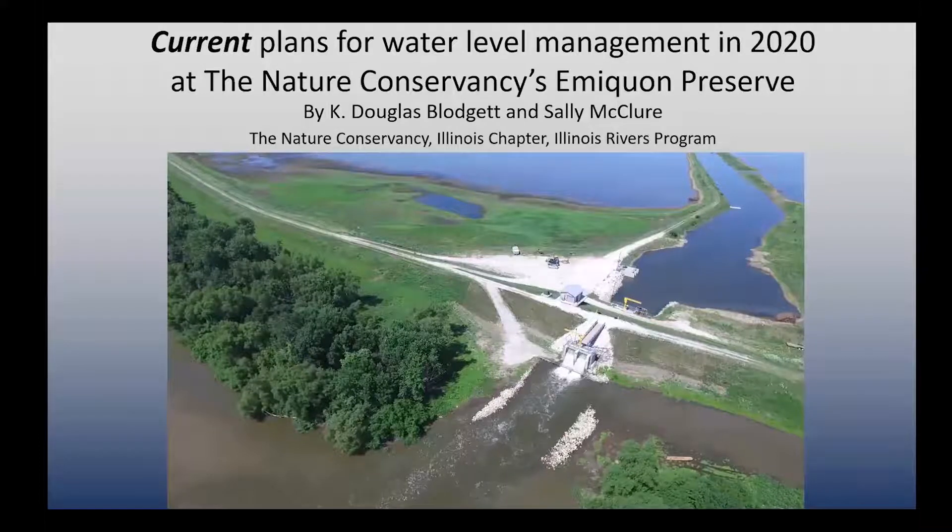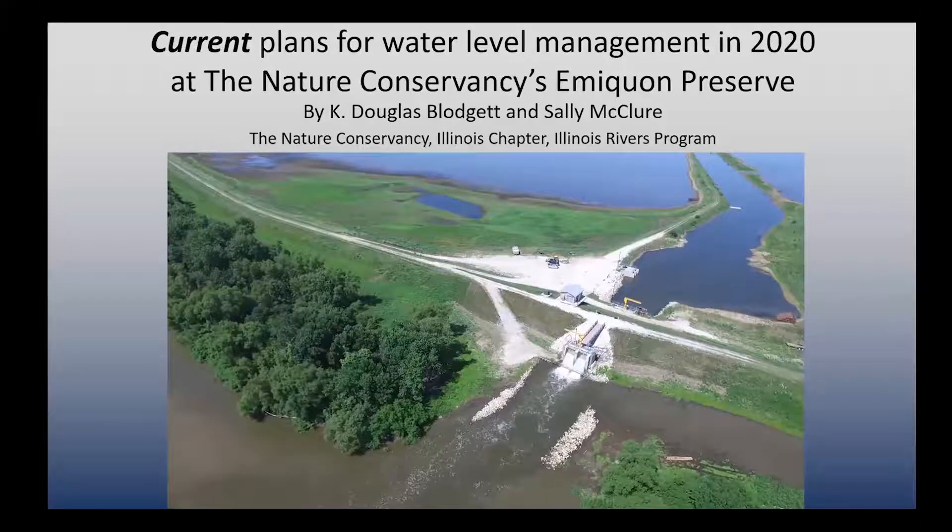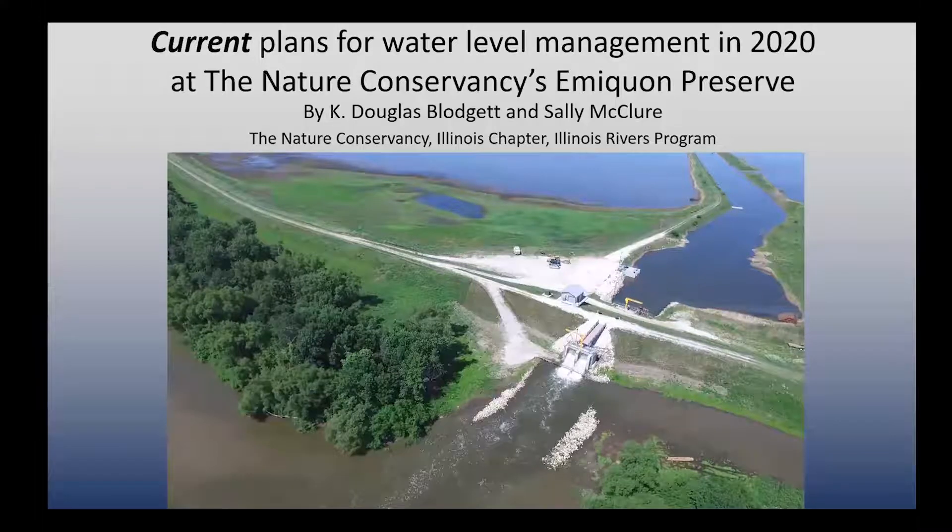The structure has two concrete culverts that are seven feet tall, eight feet wide each, about 130 feet long, and go through the levee. They provide a mechanism by which we can gravity-flow water bidirectionally — from Emiquon into the river, or from the river into Emiquon when the river cooperates.